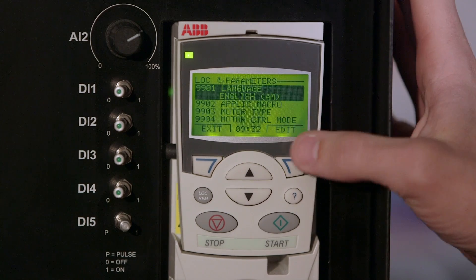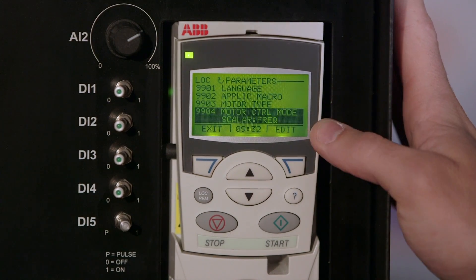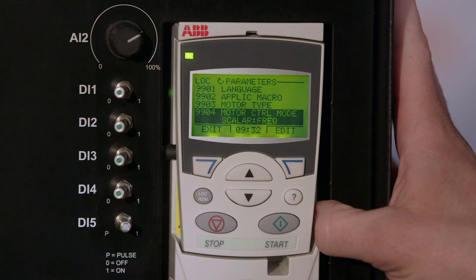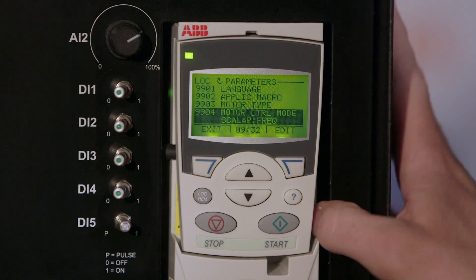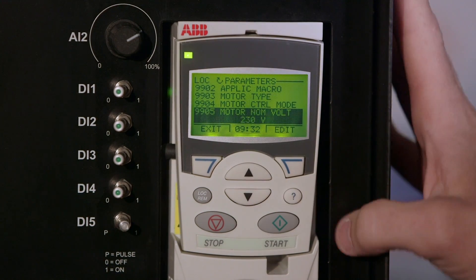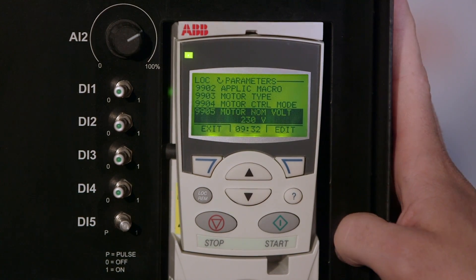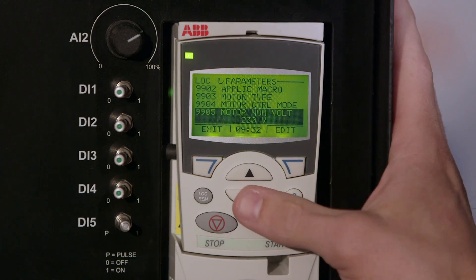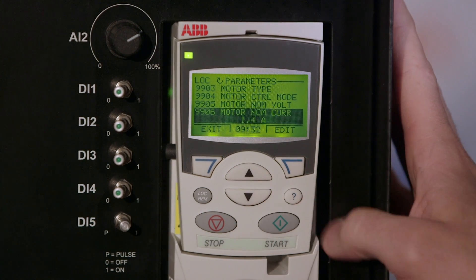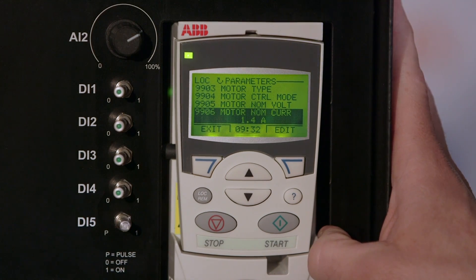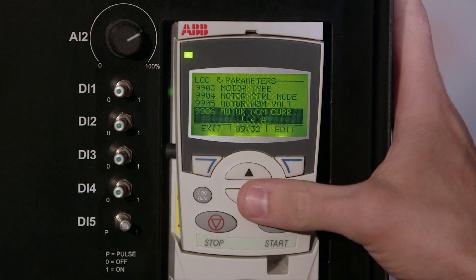We'll go down to 99.04, which is the control mode. We select scalar — it's a simpler form. In advanced applications we select vector. Then we'll scroll down to 99.05, which is the motor voltage — in this case it's 230 volts.